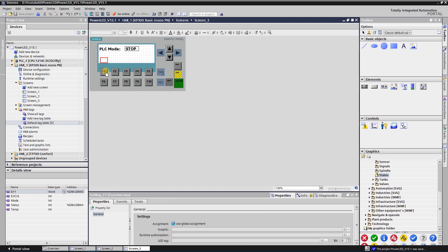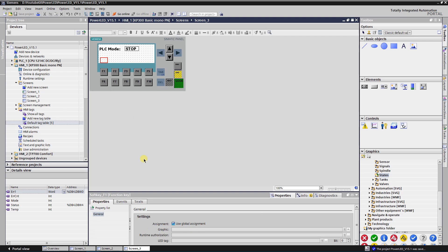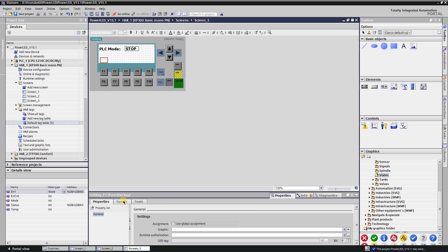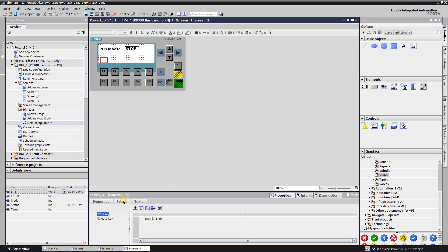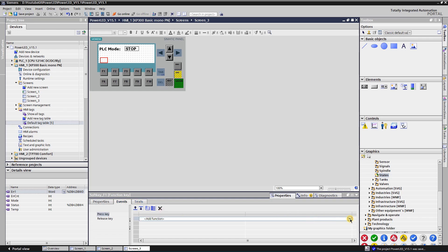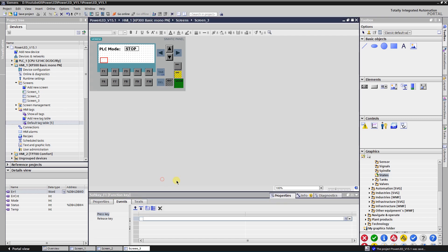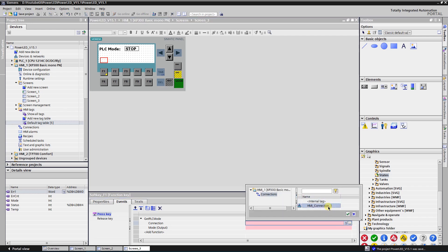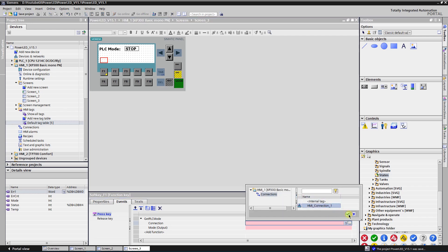Select function key F1, uncheck Use Global Assignment, and switch to the Events tab. Select the Press Key event and add function Get PLC Mode, which can be found in the functions list called Settings. Select your connection as the function's Connection parameter. Select the tag where the mode of the PLC will be stored.